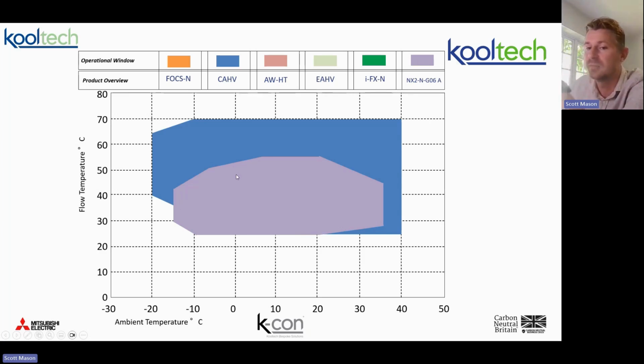A funny thing about air source heat pumps is they have comfort zones, and you can almost make an accurate prediction of the efficiency of that unit and how well it's going to work and how long the compressors are going to last based on how your performance curve lands in the profile. Do you see how the CAHV's 50-degree curve is at the bottom of its operating curve, whereas for this, it sort of scales the operating curve? So without even doing the maths, I can almost with certainty say that the CAHV's efficiency at the lower flow conditions will be equal to or worse than the NXN's.